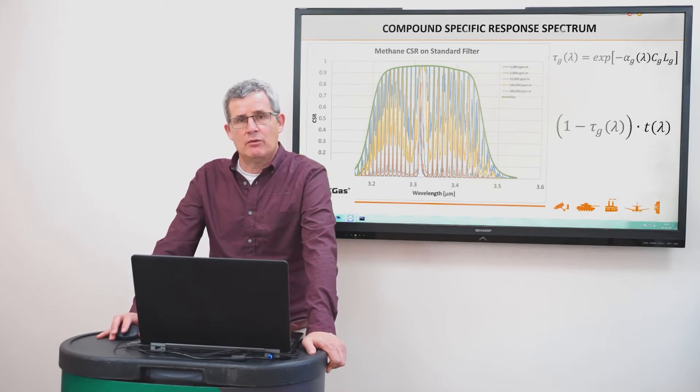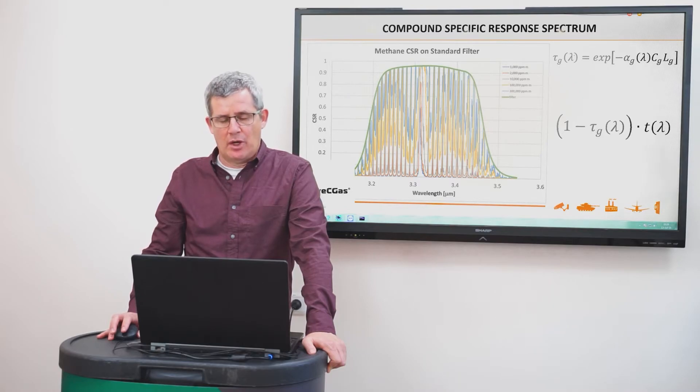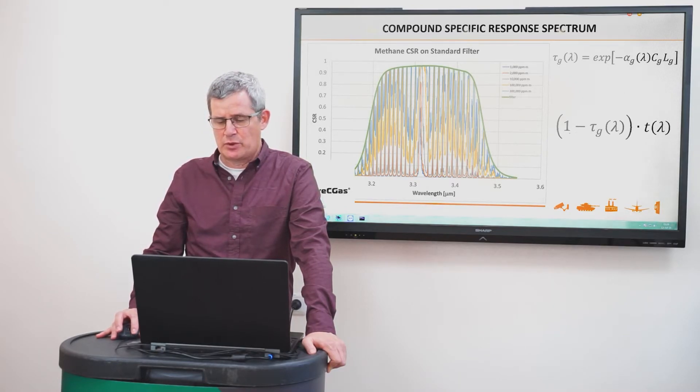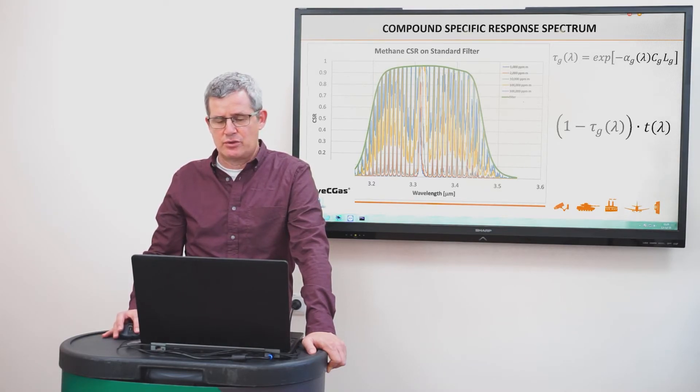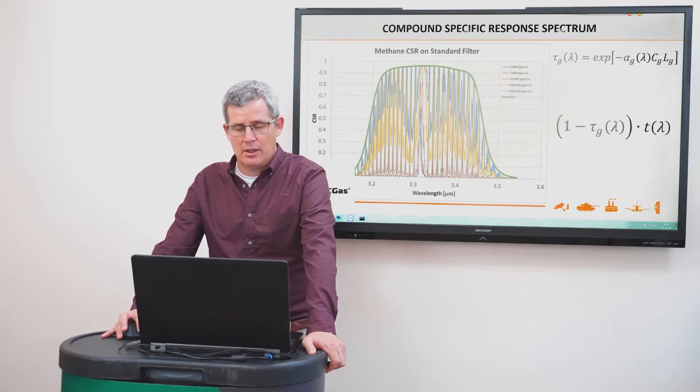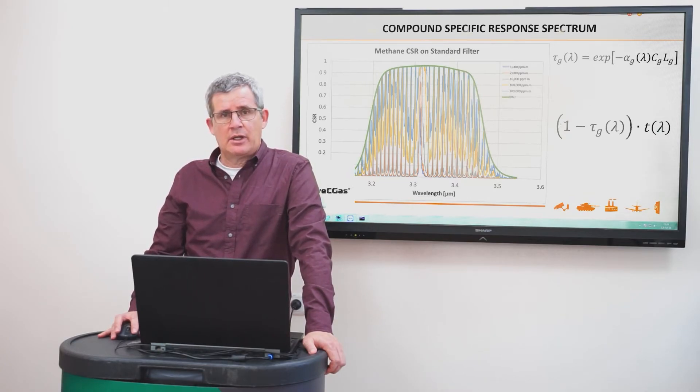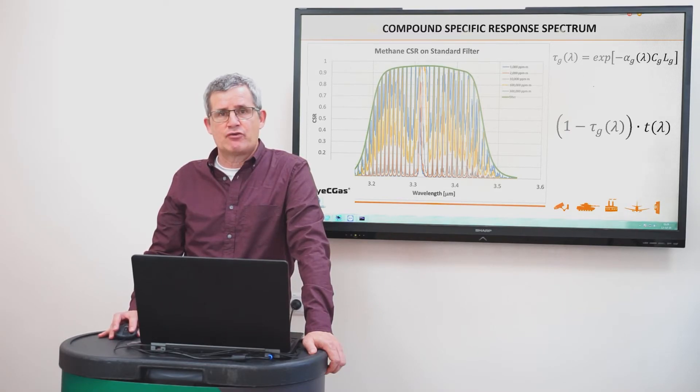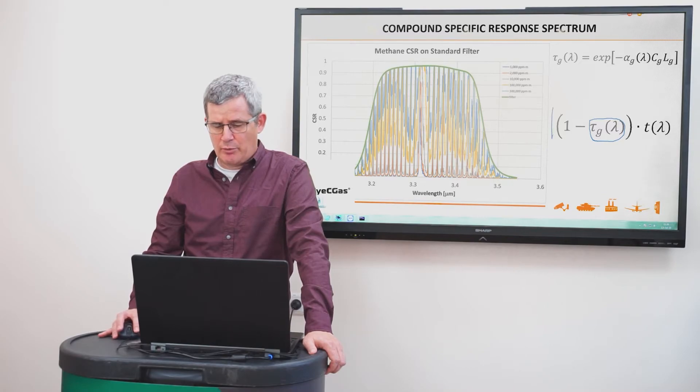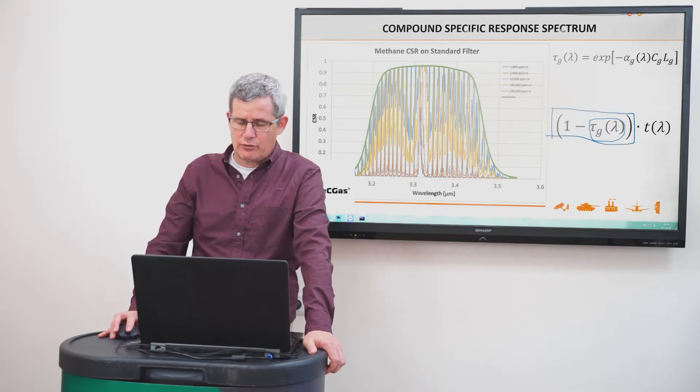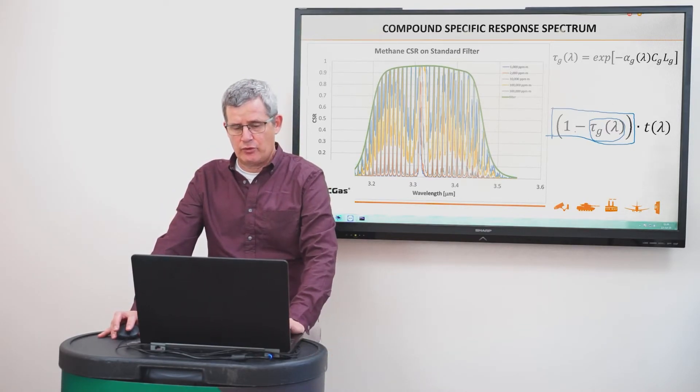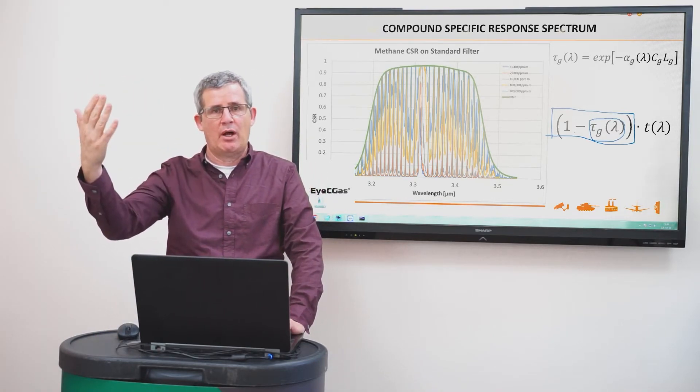So for each compound, we need to look at the spectrum of the compound specific response, which is one minus the transmission in different concentration. And here we have a plot between 1000 ppm meters to 300,000 ppm meters. And we can see as concentration going higher, it's confined by the transmission of the filter. And this compound specific spectrum can never go above one because when concentration is going very high, the transmission is going to zero. And this term of compound specific response spectrum is going to one. That means that the radiation from the background is fully blocked by the gas plume.